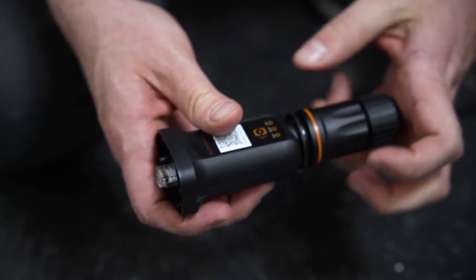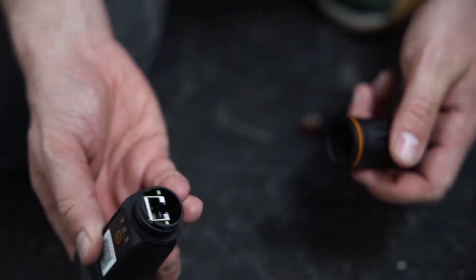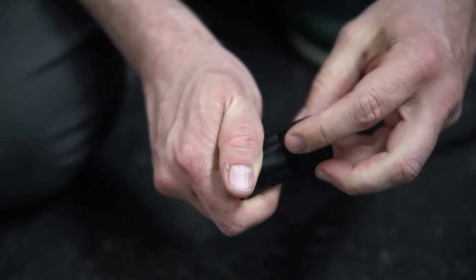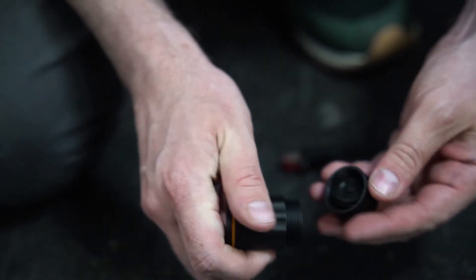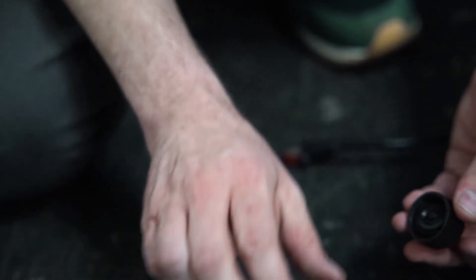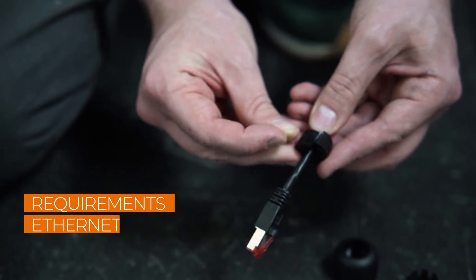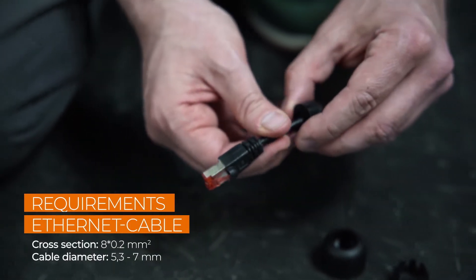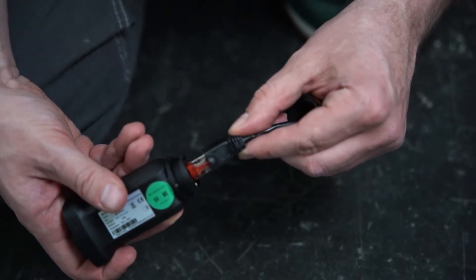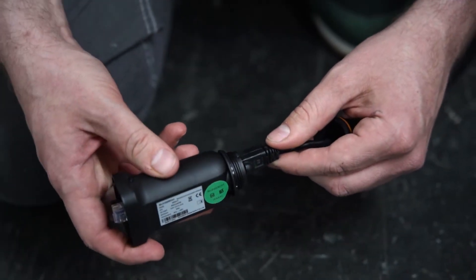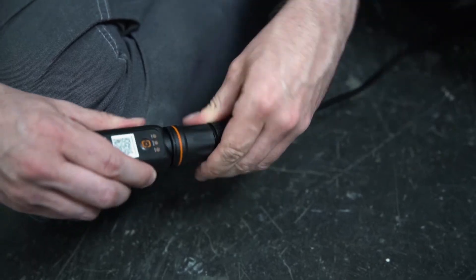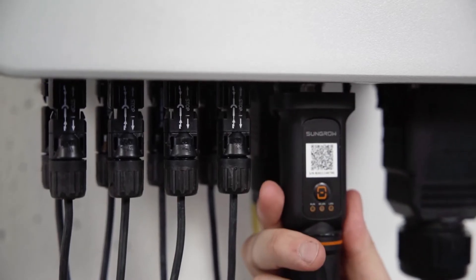After the installation of the inverter, the only required step for the commissioning is the connection via the Ethernet cable. Simply unscrew the swivel nut from the WiNet-S and thread the network cable through it. Insert the RJ45 plug into the plug connector until you hear a click. Screw everything together and plug the device in.